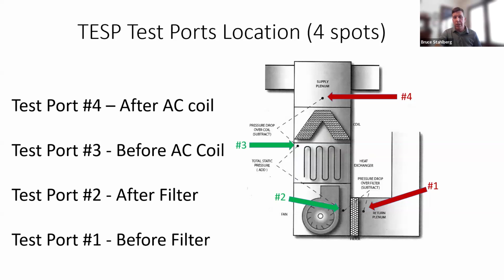Now notice I call these test ports. That's an important distinction. We're not drilling holes in the systems. People sometimes get upset. They have a brand new furnace and you're putting a hole in there. So I always call them test ports. And you tell people that, hey, you know what, these test ports should already be here. We need to do it to get the furnace set up. And that will get you out of a lot of trouble, a lot of uncomfortable conversations. So always get in your mind to call them test ports.